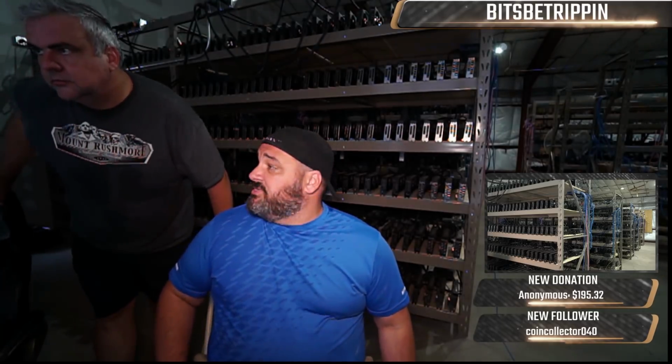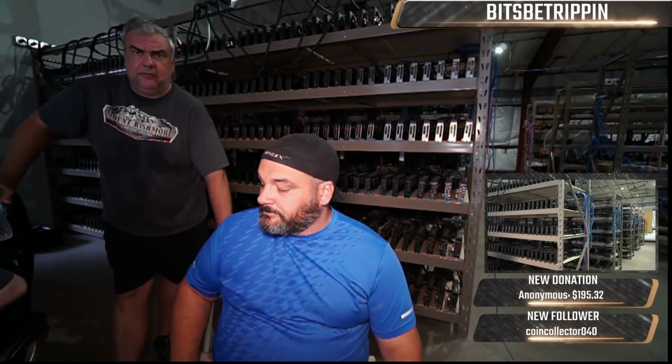No air conditioning. We're not running any air conditioning at all. It's all a very high-powered movement of air. Good ventilation, intake, and then external exhaust with 3-phase fans. Yeah, we got big 3-phase fans, which are moving about 44,000 CFM. That's quite a bit, and that's just a pair of them.